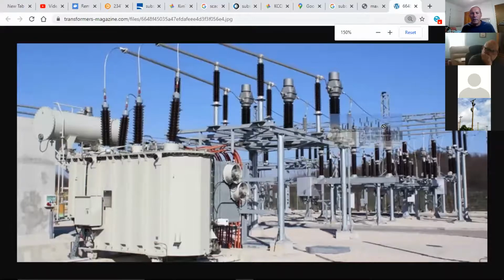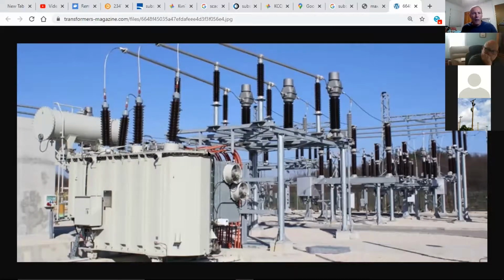Oh, excellent. Okay. Wow, this is odd. No, that'll work. So I have inbound voltage, and part of it is going to be going underground. The output of my transformer comes down here to the end of the bus, and I'm going to put a PT. So PT here, and PT here, all measuring differences in voltage. I've got a CT on the inbound and outbound of the transformer, so it's monitoring the amperage in the transformer, but I don't put a CT at the end of the bus.